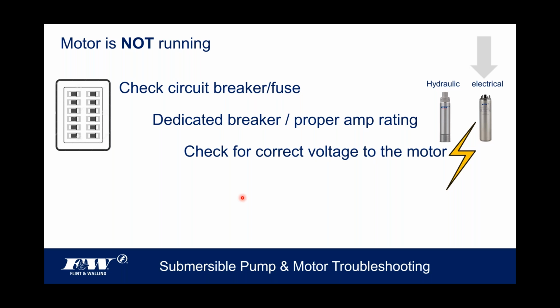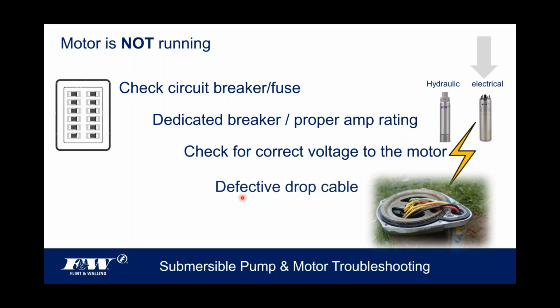If it blows the breaker, I'd say also check for the correct voltage to the motor, because incorrect voltage to the motor will also cause nuisance tripping of these breakers. And also a defective drop cable, right? If you've got a drop cable that's got pits in it, or the insulation is worn thin, it'll short out, right? So the problem could be, say, from the pressure switch down to the motor itself in the form of that drop cable.